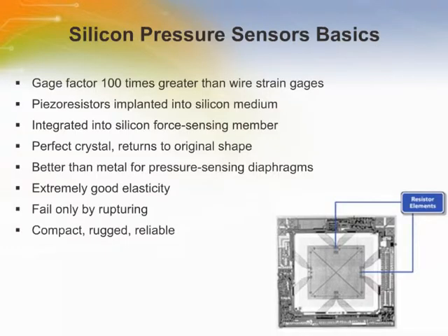Piezo resistance of a semiconductor can be described as a change in resistance caused by an applied strain of diaphragm. Thus, solid-state resistors can be used as pressure sensors, much like wire strain gauges, but with several important differences and advantages. The high sensitivity or gauge factor is perhaps 100 times that of wire strain gauges.